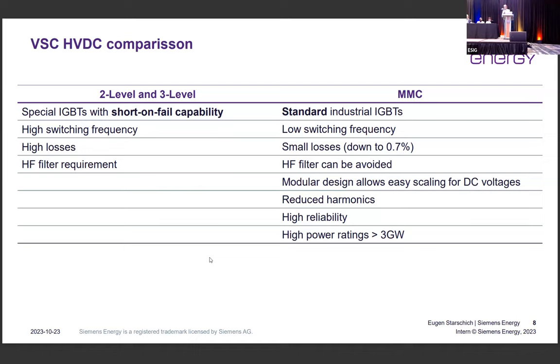It's very important that when we talk about losses, we're talking about the whole station losses. That means the transformer, the converter, all the auxiliary pumps, cooling pumps, handling units, and so on. For the MMC technology, we don't need any high frequency filters. This can be avoided by design. We have very easy scaling of DC voltages. We have significantly reduced harmonics. Harmonics are a big issue. Do we need filters? Yes or no? I would say MMC technology in itself does not need any filters, because it can provide a very good sinusoidal voltage.